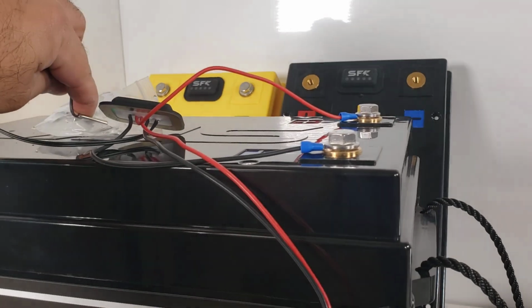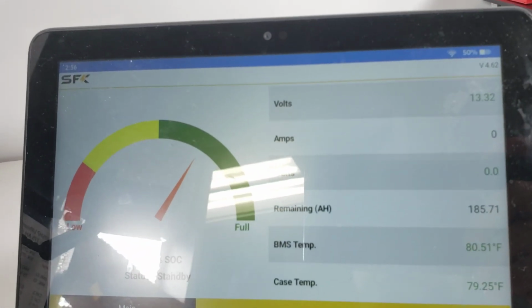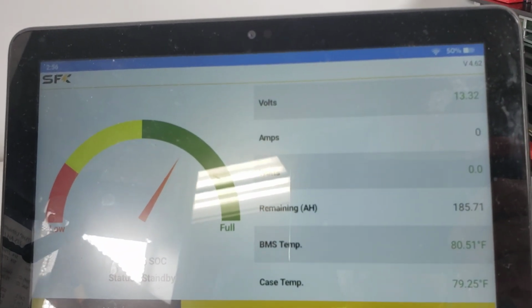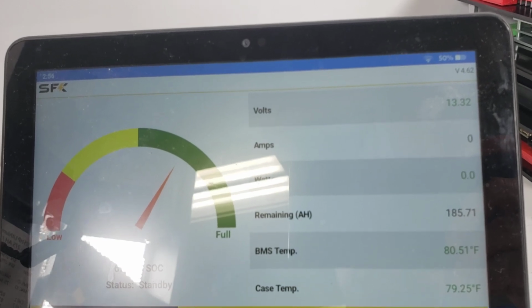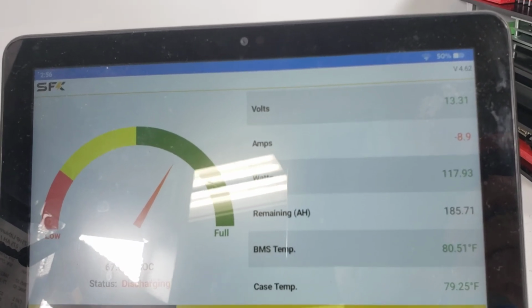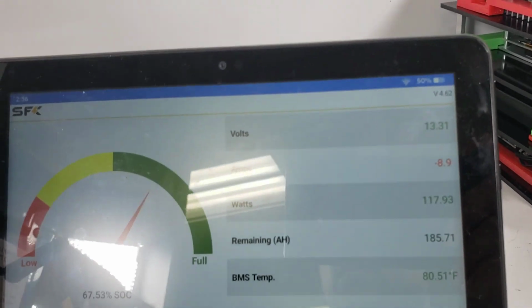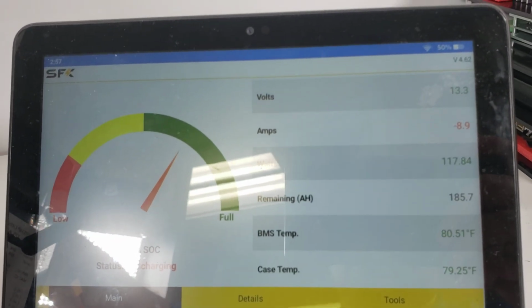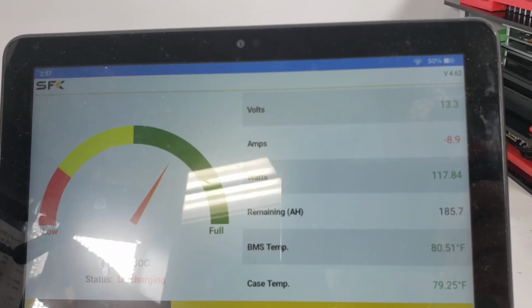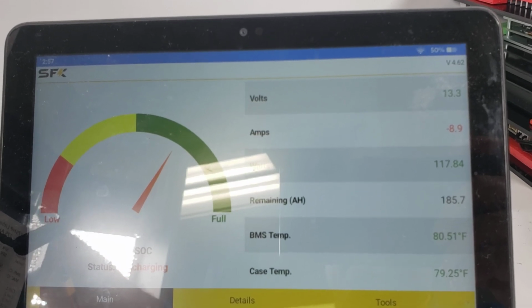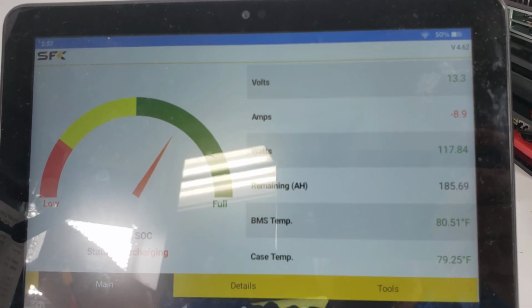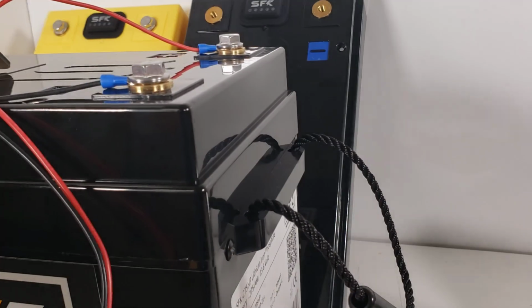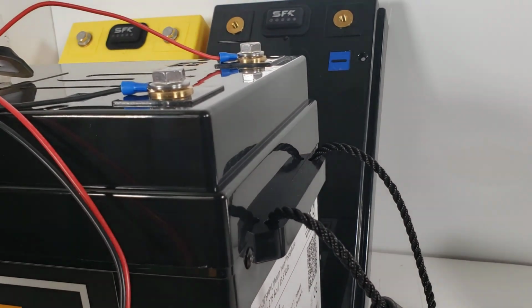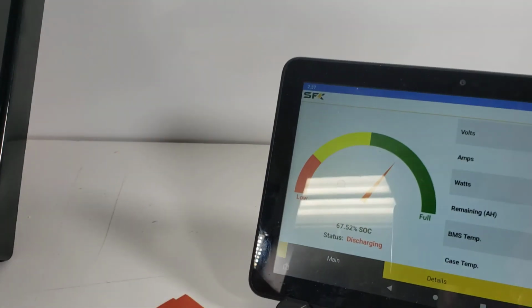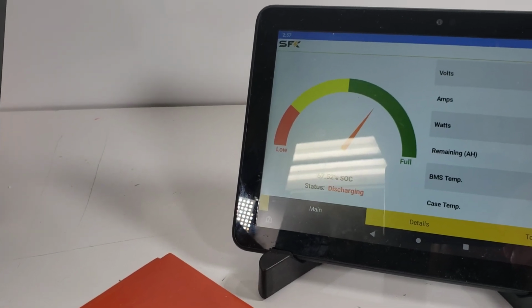So if I put it on the ice bag, you'll see it'll probably kick on in a minute. See? Yep, it kicked on. So right around 9 amps is what it's going to be drawing - 8.9, 8 point something. It will keep running until the internal temperature gets there, and then it'll cut off. Anyway, that's a little bit about that.